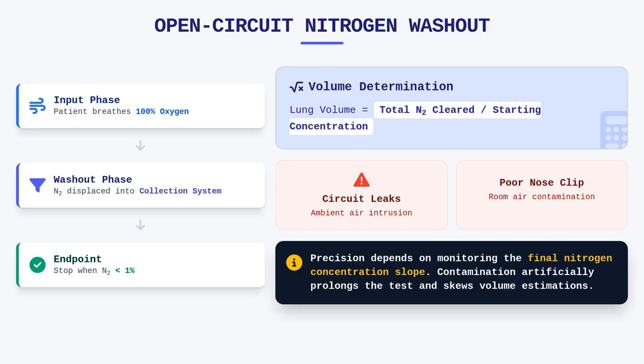Because we are tracking the clearance curve, any ambient air intrusion will artificially prolong the test or yield an erroneous volume estimation. Precision here is defined by our ability to monitor the final nitrogen concentration slope until the predetermined endpoint is met.